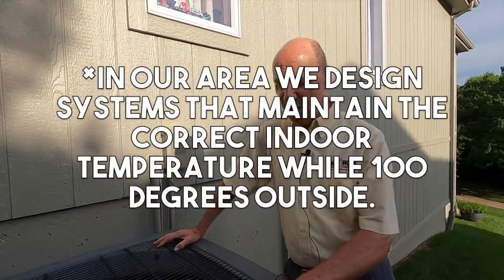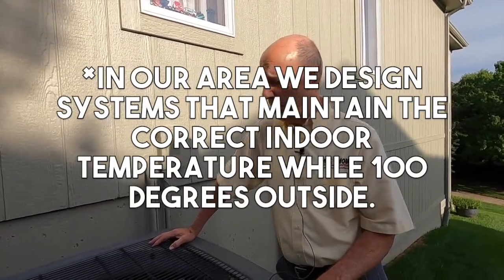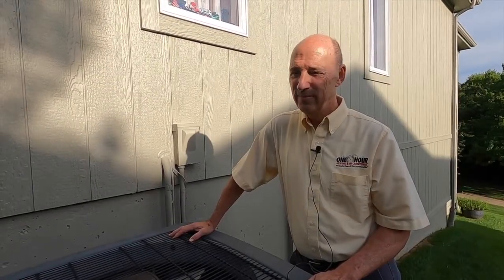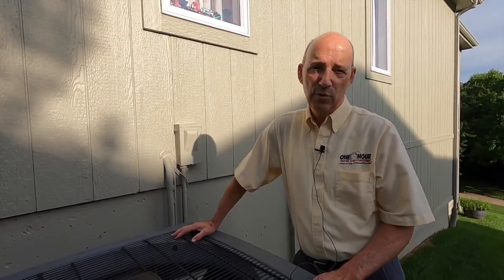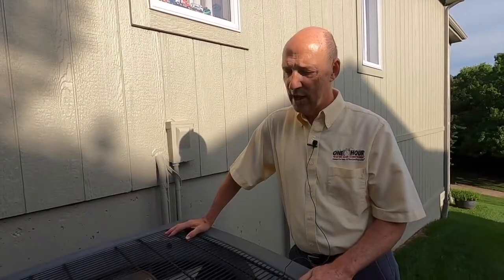So ideally, when we hit maximum design conditions, around here it's about 100 degrees, this air conditioner should be maintaining the temperature I want inside. However, it'll run all the time, and that's normal. That's normal for it to do when it's 100 degrees. If you think about any given summer, how long is it 100 degrees? Well, have we even hit 100 degrees? Some summers we don't even hit 100 degrees. The answer to that question is not very long. When it is, we want an air conditioner that can maintain a proper temperature inside.